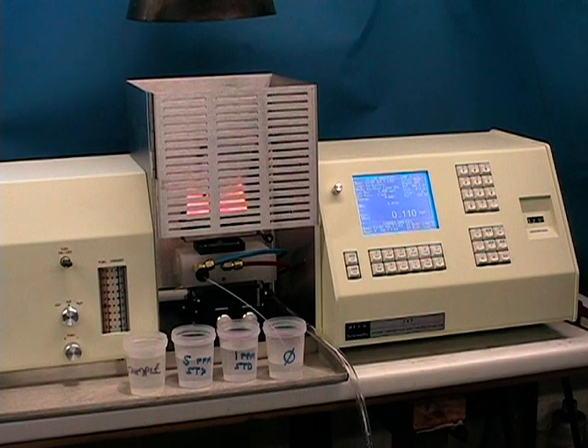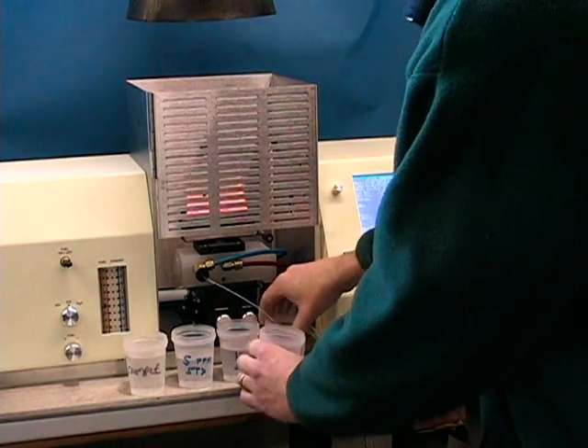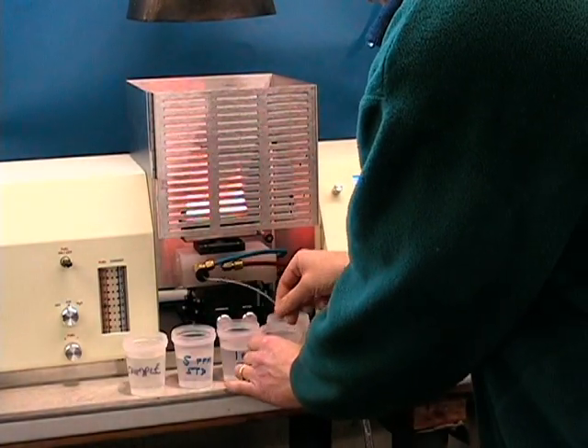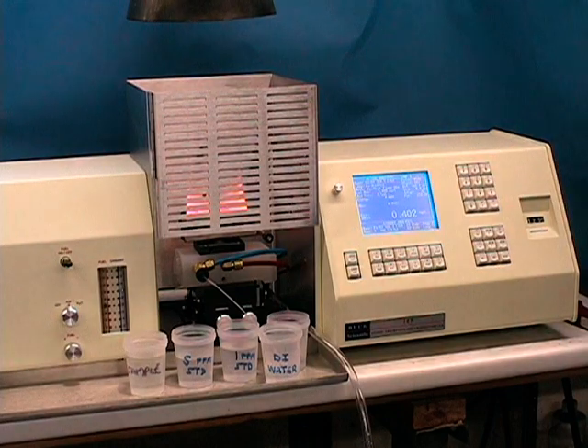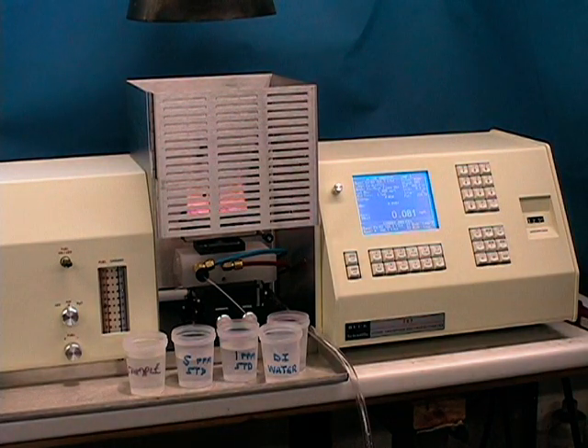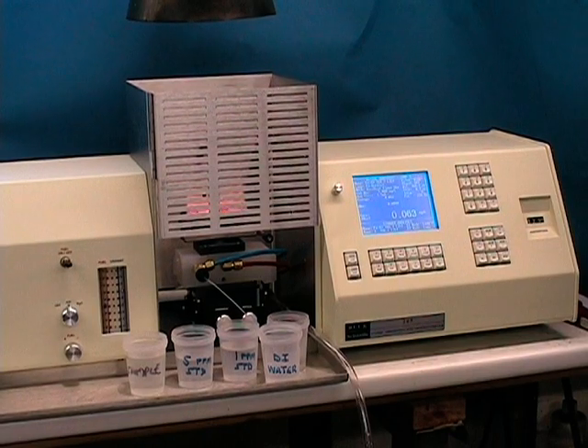At the end of your analyses, you will want to aspirate approximately 50 to 100 milliliters of deionized water to make sure that any salts, organic material, or other things that may precipitate in your spray chamber are flushed out. 50 to 100 milliliters of water should be sufficient to rinse out any residual material. It is backing up a little.